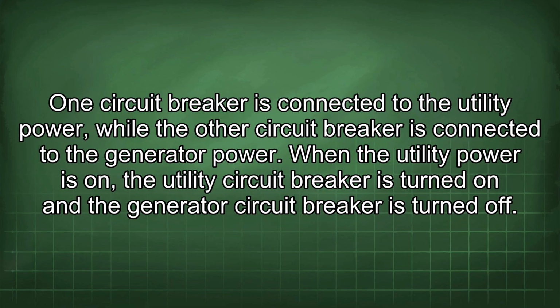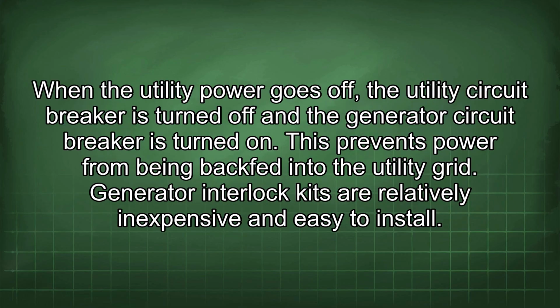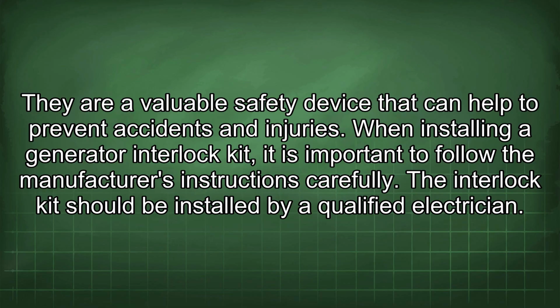One circuit breaker is connected to the utility power, while the other circuit breaker is connected to the generator power. When the utility power is on, the utility circuit breaker is turned on and the generator circuit breaker is turned off. When the utility power goes off, the utility circuit breaker is turned off and the generator circuit breaker is turned on. This prevents power from being backfed into the utility grid. Generator interlock kits are relatively inexpensive and easy to install. They are a valuable safety device that can help to prevent accidents and injuries. When installing a generator interlock kit, it is important to follow the manufacturer's instructions carefully. The interlock kit should be installed by a qualified electrician.